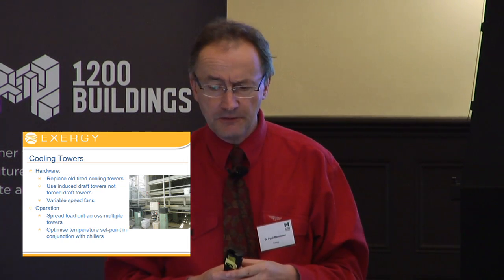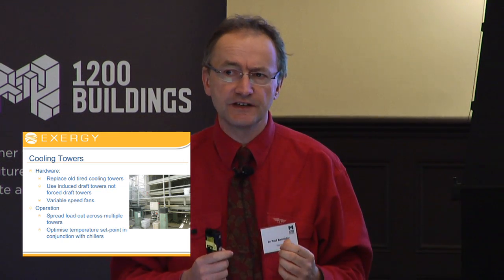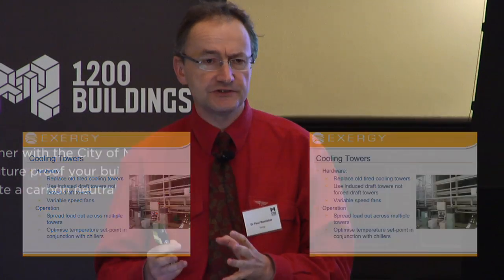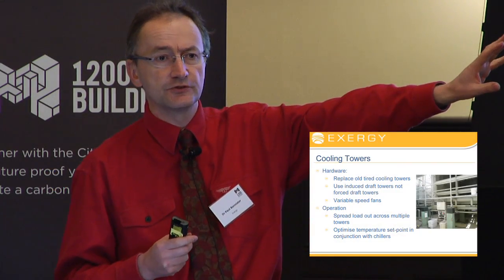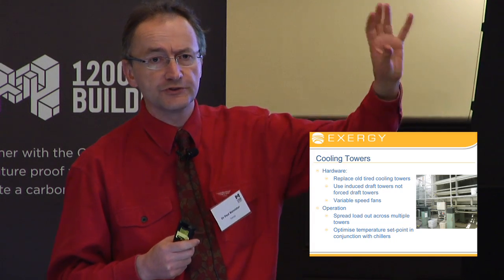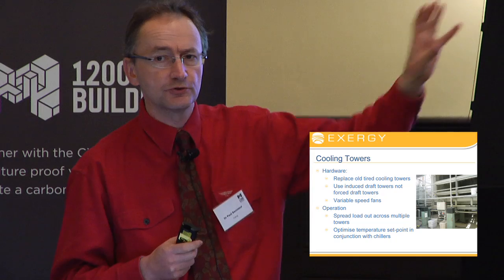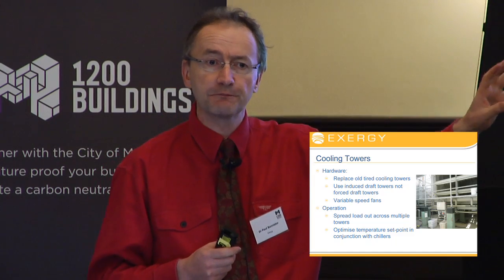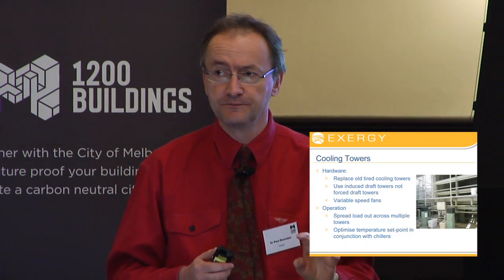To get better efficiency, spreading the load out across multiple towers typically helps. But the most important exercise is to optimize the temperature set point for your chillers. As a whole, your chillers consume far more energy than your cooling towers, so running the cooling towers a bit harder to get a lower temperature is typically a good thing. It all needs to be optimized, but as a general rule, a lower condensing temperature and harder-working cooling towers give you better performance.